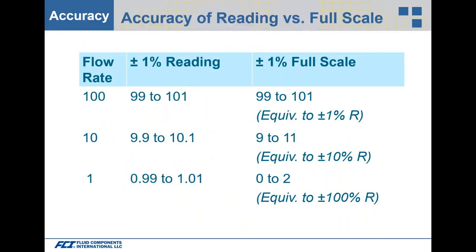Comparing ±1% of reading with ±1% of full scale: at maximum flow of 100, both give 99 to 101 — they're the same. But at low flow of 10, ±1% of reading gives 9.9 to 10.1, whereas ±1% of full scale gives an allowed error of 9 to 11. At 1 normal cubic meter per hour, ±1% of reading gives 0.99 to 1.01, but ±1% of full scale allows anywhere from 0 to 2. That full scale error really affects the allowable error at low flow.